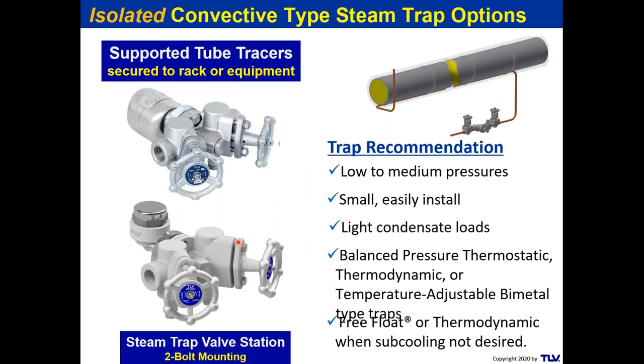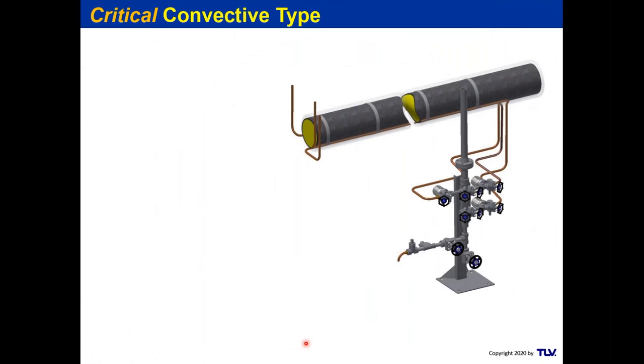Another approach for supported applications is a trap valve station, which integrates a lot of functionality in a small package: inlet and outlet isolation valves, an upstream strainer with blowdown valve, and a test port at the bottom to relieve pressure and check flow on the outlet side of the trap. This makes maintenance and operation much more efficient.